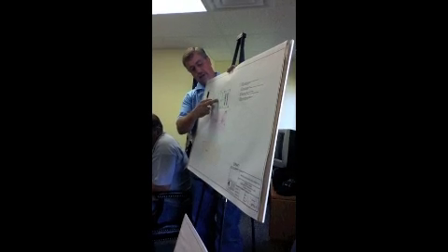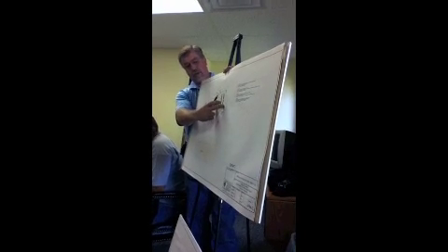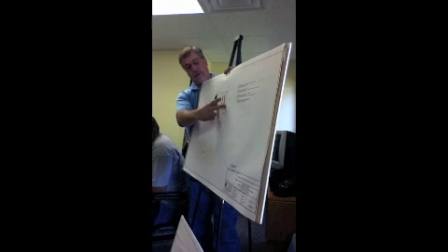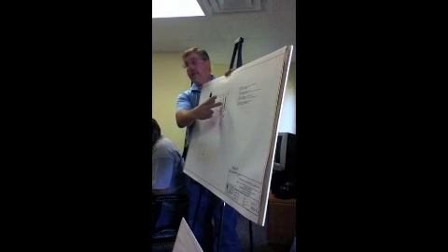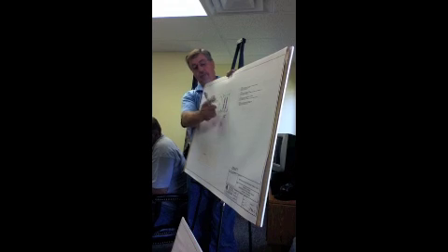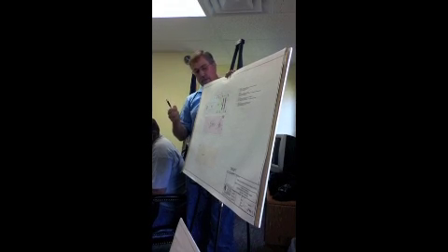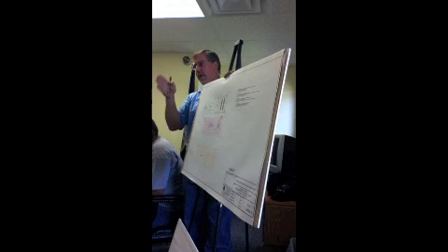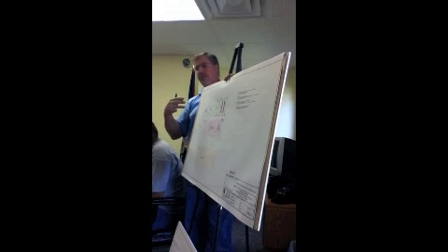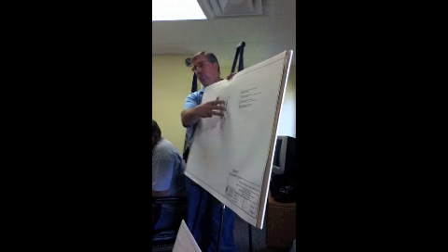You have an equalization tank now, which pumps the flow into this, your same thing, your biological reactions taking place in this tank, but this tank never shuts off. These flat membranes, there's 800 altogether, have pumps on them that pump through. It's basically like a filter, but it's a definite membrane, a definite barrier, which is the same as the microfiltrations which are being removed. So this system here is tertiary treatment and secondary treatment, biological treatment. It's all done in one tank.